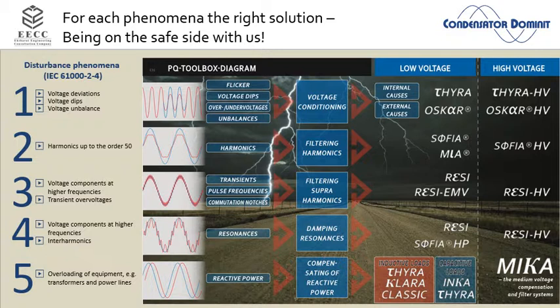As Johan was also saying, small voltage fluctuations which I cause myself, I can compensate with a normal StatCom, just pushing in capacitive current. But if it's a 30% voltage dip coming from upstream, there's not much I can do with a capacitor bank. So that's the only question: if you have a problem with the height of the voltage, are you producing it yourself, or is it coming from the public grid? If you do it yourself, I sell you some power factor correction, StatCom, capacitor bank, whatever. If it's coming upstream, we need a system with a series transformer.